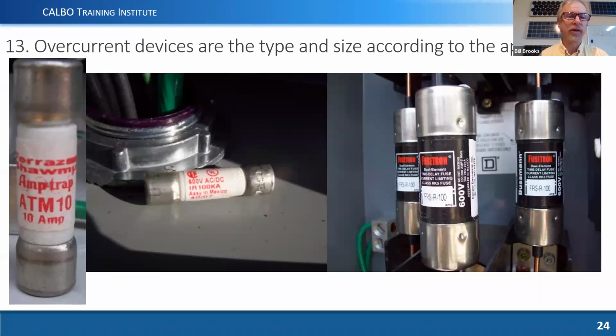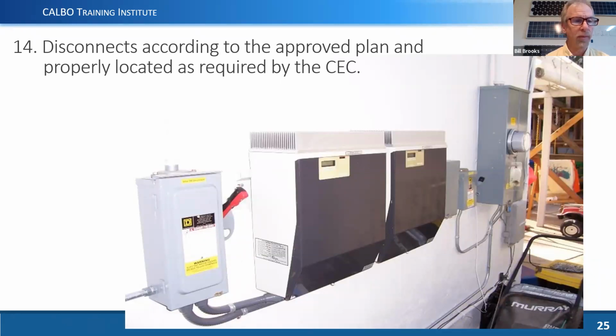Overcurrent devices in residential are almost non-existent nowadays, other than circuit breakers in the main panel and arrangements like that. But if you do have a situation where you're having to have string fuses and things like that, which would be more common in commercial installations, make sure that the ratings are correct. So this is a 600 volt AC/DC fuse, which would be used in residential applications. This is a 600 volt fuse over here, a class R 100 amp fuse, but it's only a 300 volt DC fuse. So it would not be allowed in an installation that was over 300 volts, which is very uncommon to have. But also, most of our commercial systems are at 1,000 volts now with 480 volt three-phase output. So 1,000 volt equipment would be necessary, of course, in those installations. Disconnects according to the approved plan.